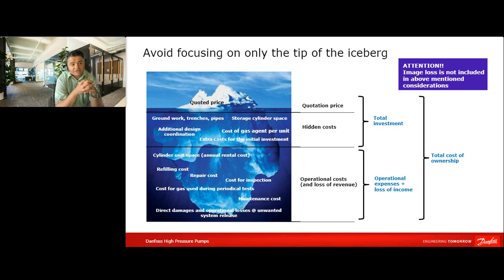And just imagine that if the detection system has a malfunction or gives a wrong signal, even if there is no fire or smoke inside it, then after maximum 1 minute, the gas extinguishing system is activated and the gas is released into those rooms. Nothing happens. There's no damage of fire or whatever, but you have to refill all those cylinders again, and then you have to clean up those areas. You have to stop the operation.